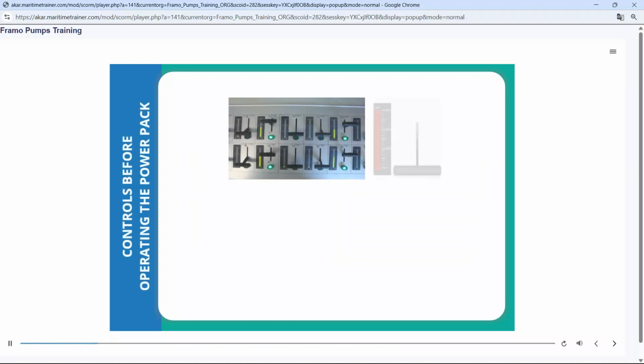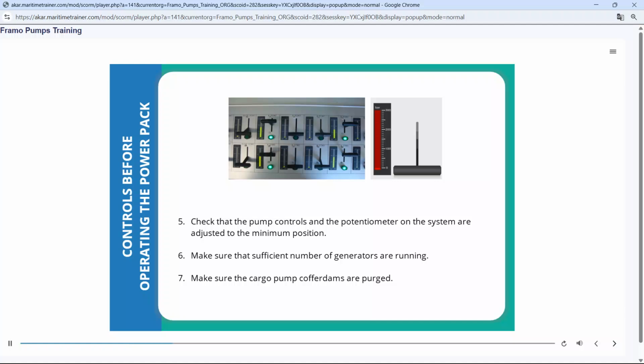Check that the pump controls and the potentiometer on the system are adjusted to the minimum position. Make sure that a sufficient number of generators are running. Make sure the cargo pump cofferdams are purged.